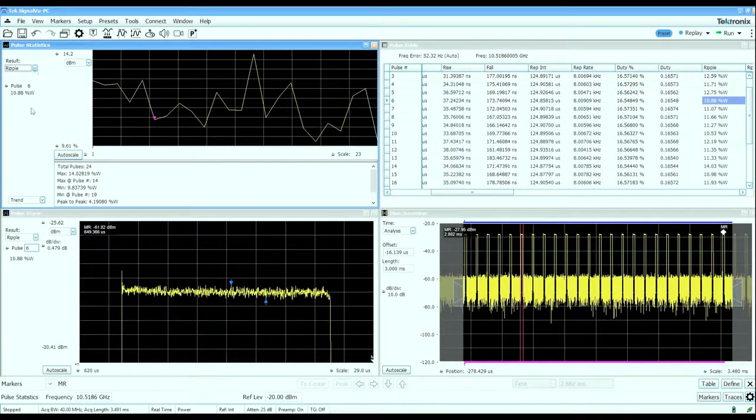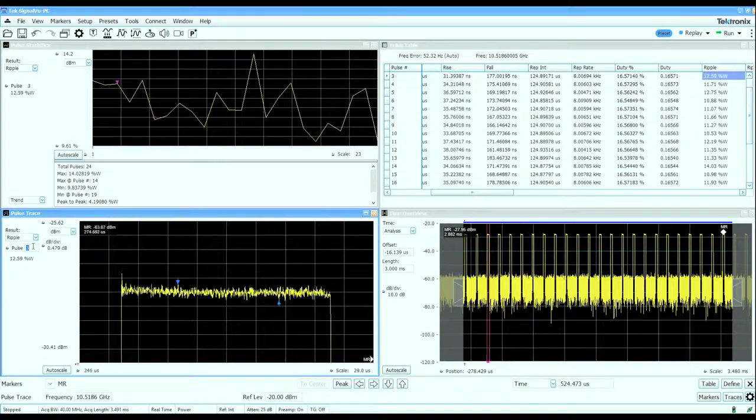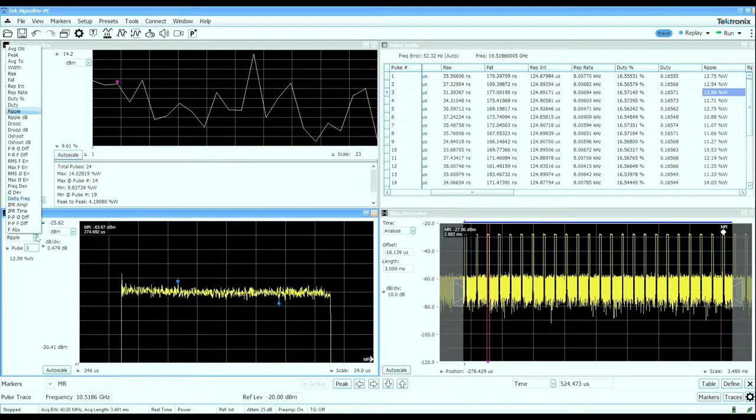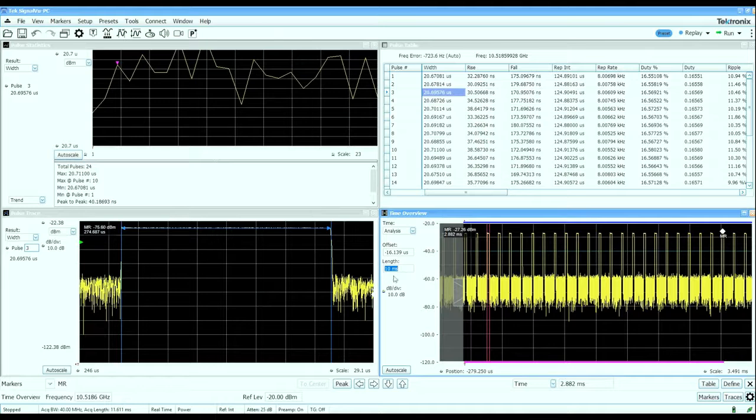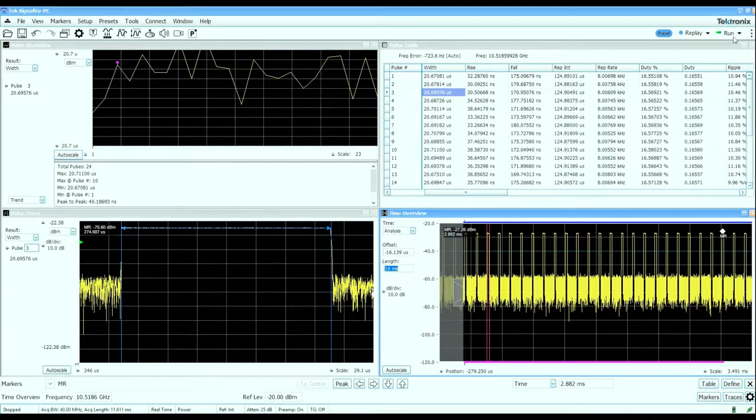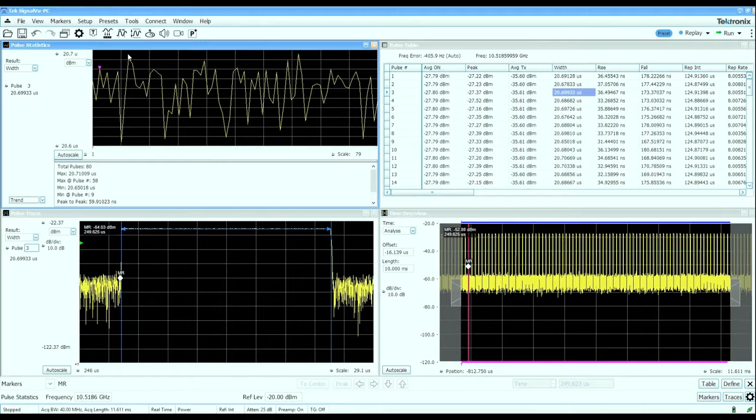I can pick those measurements and then walk my way up and down the table for any of those particular measurements. We've changed the analysis length now to 10 milliseconds and let's do a single capture of that.